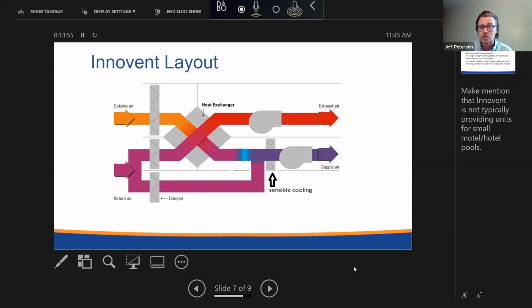From a pressure control standpoint, we're always maintaining that pool space at a slight negative. That's very important. With chloramine-laden air, you don't want that air leaking into adjacent party rooms or lobbies or things like that. You want air from adjacent spaces to leak into the pool room.